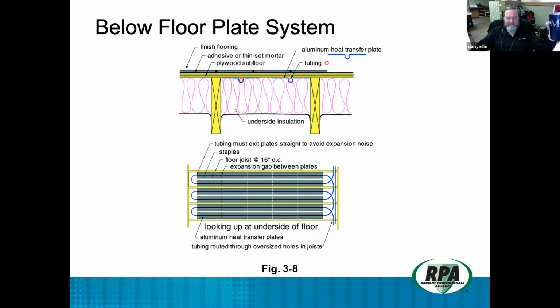Typically 115 degrees is going to be the maximum temperature that you'd be able to get out of it. Now, we have a lot of hybrid systems. The problem with having a ground source heat pump system is that if you're doing domestic hot water preheat, 115 is not hot enough for end use. So we need something to raise it the rest of the way.